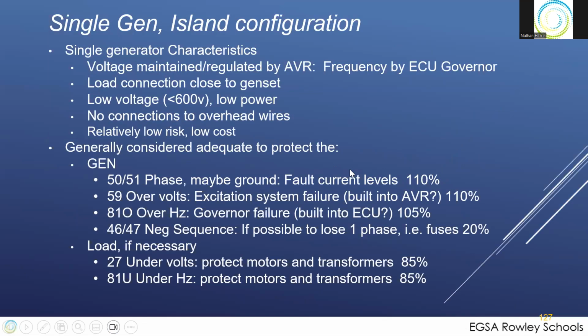So let's talk real quick about a single island configuration. This is the protection that's kind of recommended to help get you started. If you don't have settings, you didn't do your power system setting, you've got to test your generator out. If you set it here, you'll be okay. Don't leave it there, put it back. But this will get you by in a pinch.